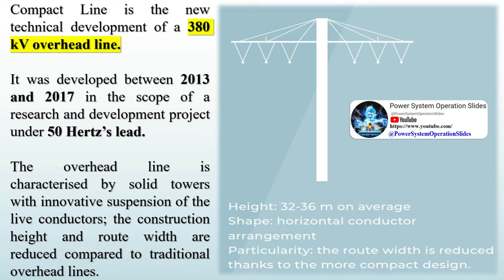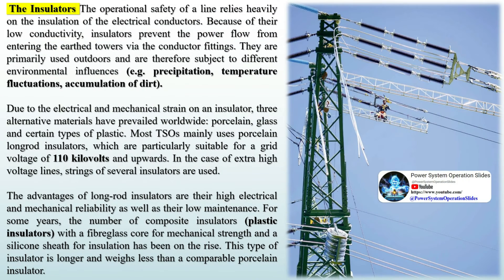The operational safety of a line relies heavily on the insulation of the electrical conductors. Because of their low conductivity, insulators prevent the power flow from entering the earthed towers via the conductor fittings. They are primarily used outdoors and are therefore subject to different environmental influences such as precipitation, temperature fluctuations, and accumulation of dirt. Due to the electrical and mechanical strain on an insulator, three alternative materials have prevailed worldwide: porcelain, glass, and certain types of plastic. Most TSOs mainly use porcelain long-rod insulators, which are particularly suitable for a grid voltage of 110 kV and upwards.